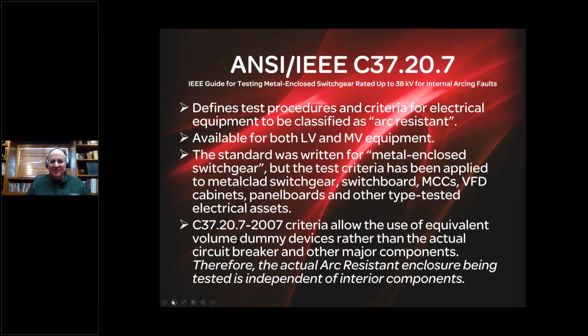Once you follow the test standard, that definition in C37.20.7 has been applied. And one of the most important points I want to make in this entire presentation is the final point at the bottom of this slide. So C37.20.7 allows the use of equivalent volume dummy devices rather than actual circuit breakers and other major components. Therefore, the actual arc-resistant enclosure being tested is independent of the interior components. Going back to my earlier point, this is about maintaining enclosure integrity and not allowing hot gas and plasma to be ejected from vents and seams or failures of the enclosure itself, whether it's a bolted panel or a hinged panel breaking open.